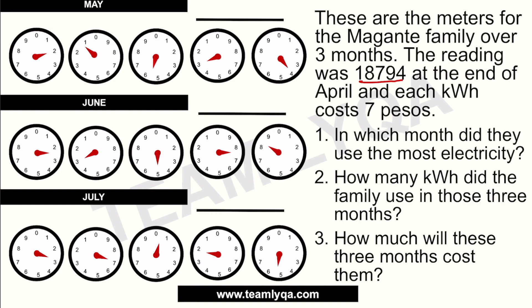As discussed in the first video, when reading a meter, we look at where the arrow is pointing, and if it's between two numbers, we take the lower one. For May's first panel: 2. Between 1 and 2: 1. Between 5 and 6: 5. Then 3, and 4. So the May reading is 21,534. Subtracting the April reading of 18,794, their consumption in May was 2,740 kilowatt hours.